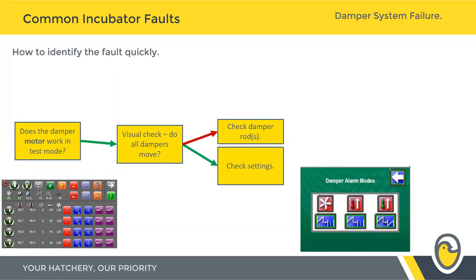The last settings to look for on the damper are the three interlocks, which dictate how the damper behaves under three separate alarm conditions. The one on the left is a fan fail alarm — we always recommend that's enabled, so if your main fan fails, the damper opens quickly to get fresh air through and keep the cabinet cool. The second is a high temperature alarm working on the mercury-free over-temperature or independent over-temperature alarm. The third is a high humidity alarm — personal preference on those last two whether you want them open or not.